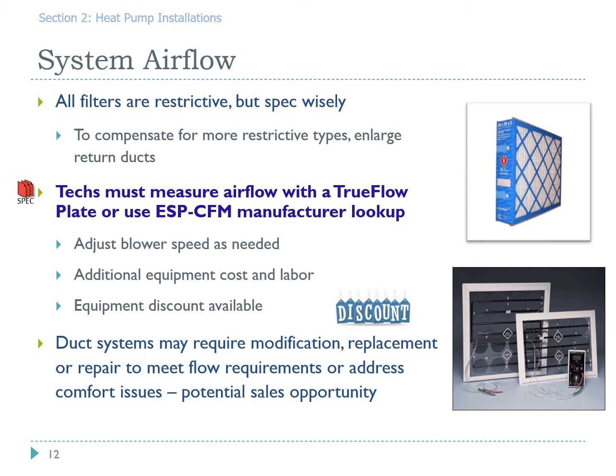Continuing with system airflow, the selection of filters is really an important piece to think about. So all filters are restrictive, but some are more restrictive than others. And if you select a very restrictive filter, you may need to compensate by enlarging the return air duct to be able to meet that system airflow specification. So one of the specifications we have is that the technician must measure the airflow with either a true flow plate or the external static pressure CFM manufacturer's lookup table. And so with the true flow plate, we have discounts available, and we'll talk about that a little bit later.